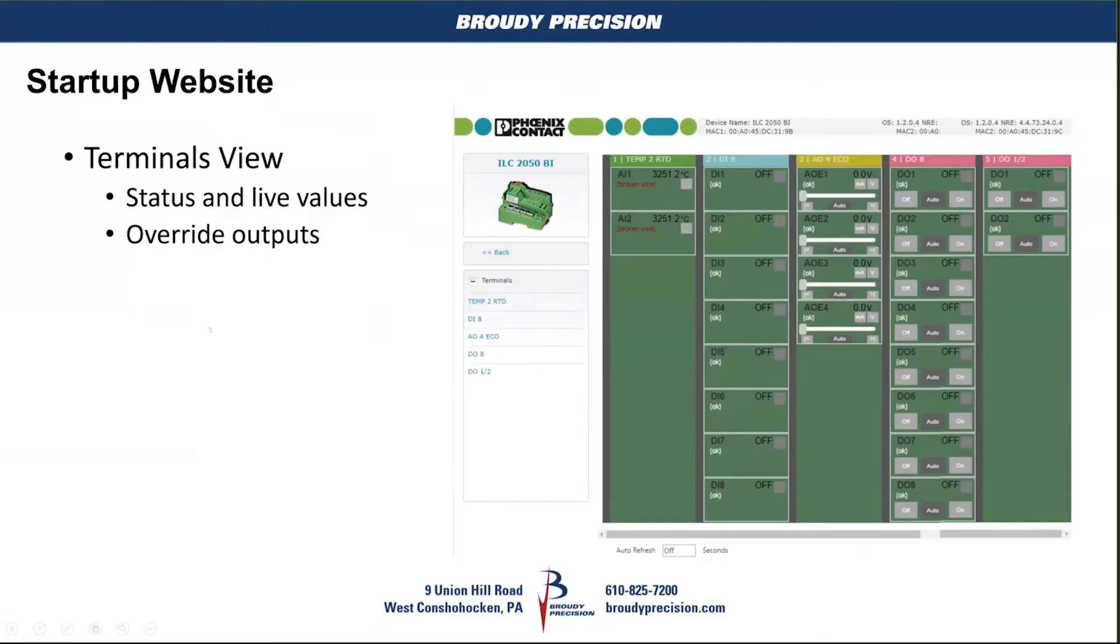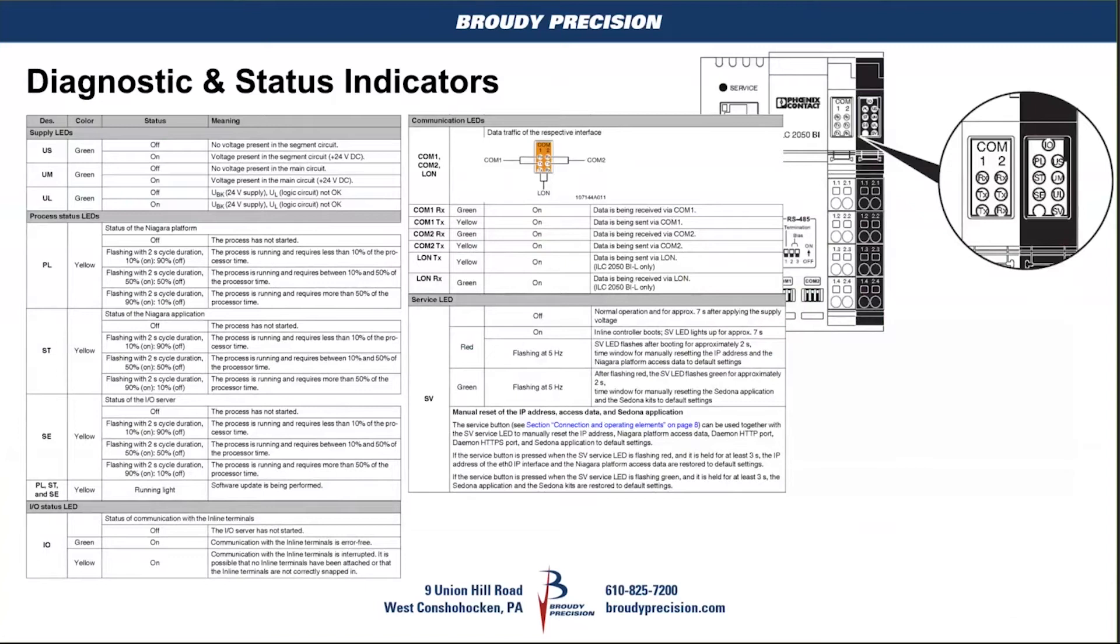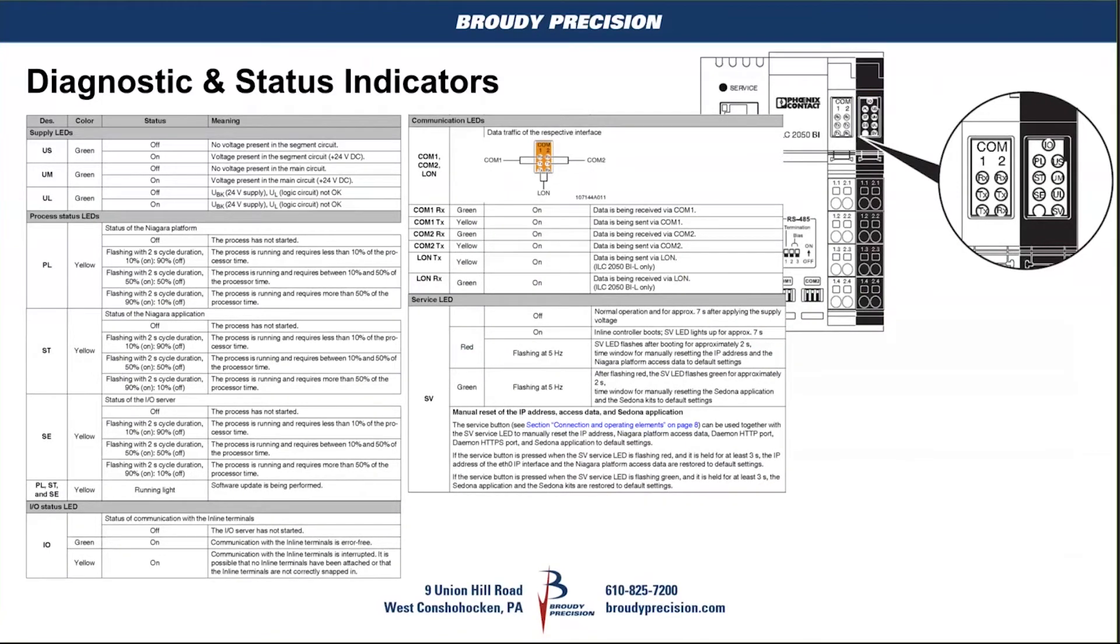Out of the box, what does it want to use as a temperature? When you bring them in, you tell it, you have to select what you want. Depending on which card you buy, for webs it wants to be a 20K, for RIO it wants to be 10K. Does this thing have a particular, just RTD? Their standard is an RTD, like PT100, PT1000 type thing.